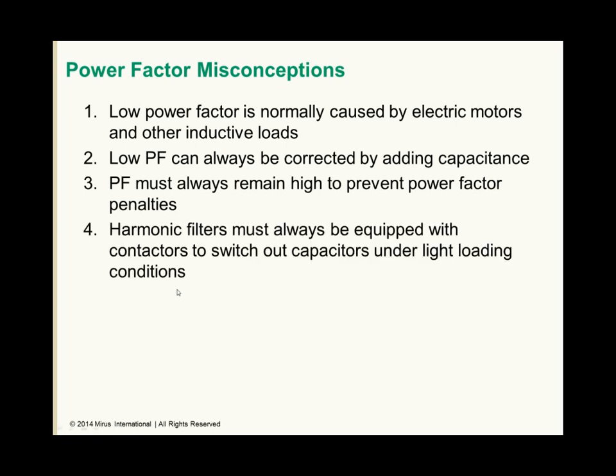Fourth one is that harmonic filters must always be equipped with contactors to switch out capacitors under light loading conditions. Many harmonic filters do require switching out contactors under light loading, but a properly designed one does not have that requirement.